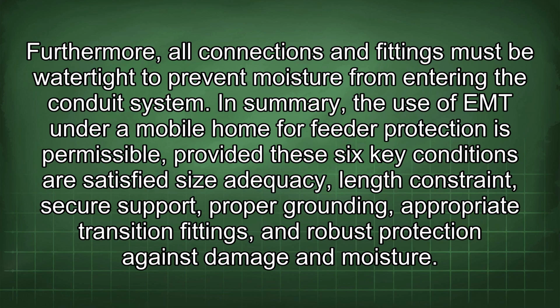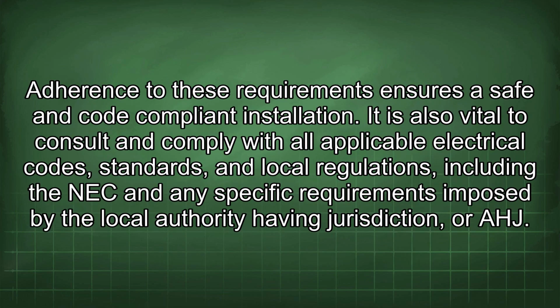In summary, the use of EMT under a mobile home for feeder protection is permissible, provided these 6 key conditions are satisfied: size adequacy, length constraint, secure support, proper grounding, appropriate transition fittings, and robust protection against damage and moisture. Adherence to these requirements ensures a safe and code-compliant installation.